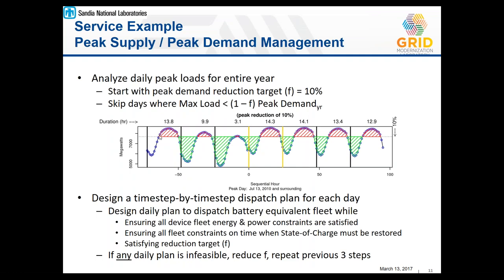We would start at the beginning, and we would go through each time step and ask the battery equivalent model, can I supply this service? The battery equivalent model then responds, yes, I can supply this service. I can discharge and offset this load by this much. It then updates the device-specific model, which then updates the parameters for the battery equivalent model, and we step forward in time, supplying the next service, and where the grid service asks, can you supply this one?